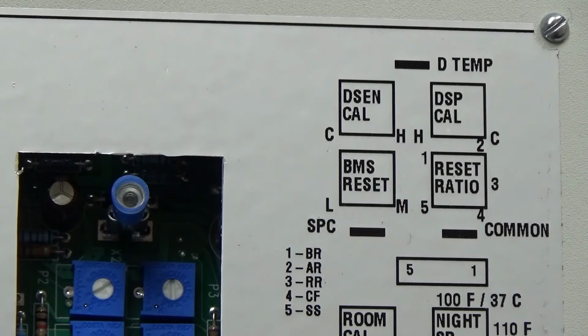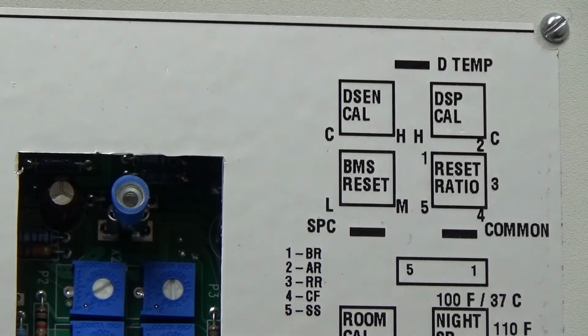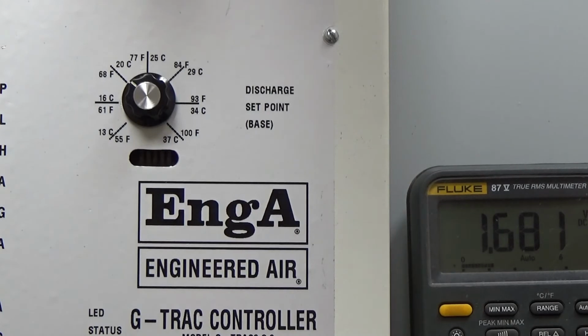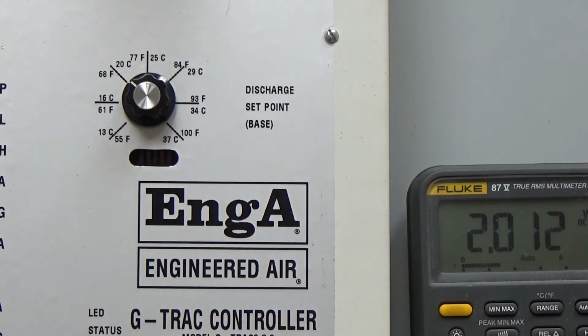To calibrate the discharge set point, locate the pot labeled DSP Calibration. With a pocket screwdriver, adjust the DSP calibration pot until your voltage reading matches your discharge set point dial. Once your voltage reading matches your set point dial, your set point is calibrated.